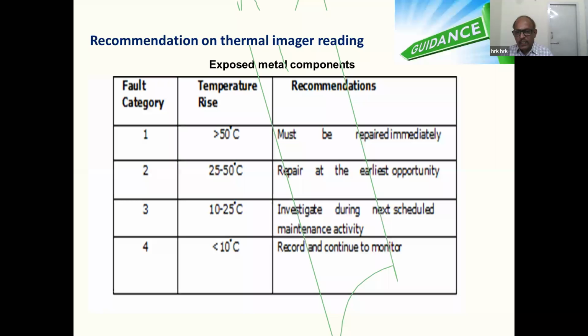If it is 25 to 50 degrees, we have to take corrective action at the earliest opportunity, because all the plants cannot be switched off immediately whenever you find an abnormality. So we wait for the end of the shift, the end of the week or the end of the batch, and then take the immediate replacement. If it is more than 50 degrees above the atmosphere, say 80 to 90 degrees when the ambient is 32, then there is some serious problem, which we will see later, that can come in an electrical system. They have to take immediate corrective action, otherwise it may result in failure of the equipment or a huge fire.